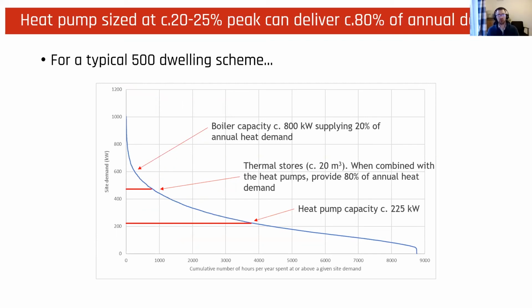So, for example, using the same 500 dwelling scheme example, we can actually provide 20 to 25% of the peak demand through heat pumps by sizing them, say, 225 kilowatts. But in combination with a thermal store of around 20 meters cubed, we can meet 80% of the annual heat demand. Then to provide that additional 20%, we have the boilers doing some peak loading. It can either be a gas boiler, or it could also be an electric boiler, depending on the constraints on the site and whether gas is in the mix or not.